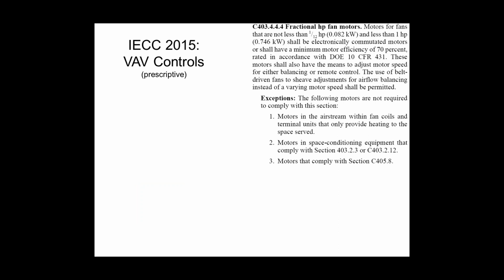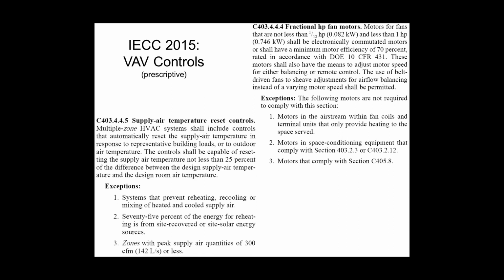On small systems, on a VAV system, small fans, specifically between 1/12 horsepower and 1 horsepower, you have to use an ECM motor, right, for either direct controllability or for balancing purposes, but you have to have that more efficient ECM motor in there. And specifically, the interesting note is motors in the airstream within fan coils and terminal units that only provide heating to the space served, right? So that has lately been interpreted as: if you have a parallel fan-powered box that provides heating to the space served, you don't have to do the ECM motor. If you have a series fan-powered box, it is running for both heating and cooling modes, and hence it does have to have an ECM motor. So that's the way we've been looking at that one thus far. So ECM motors on series fan-powered boxes, as well as for fan coils.